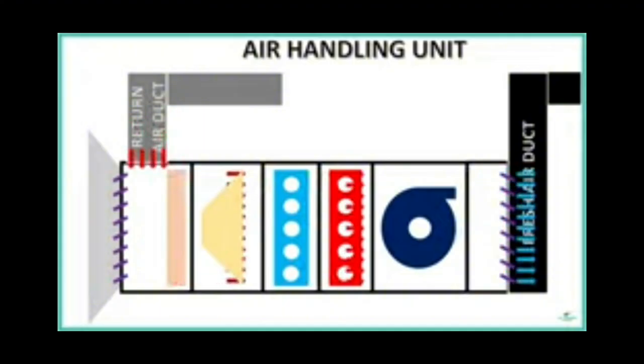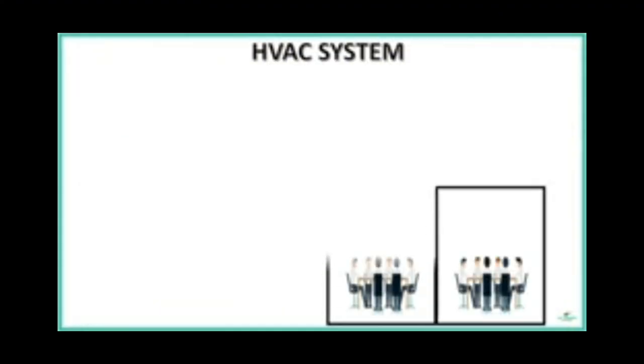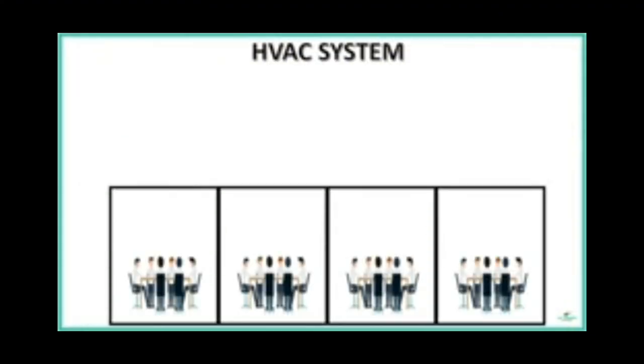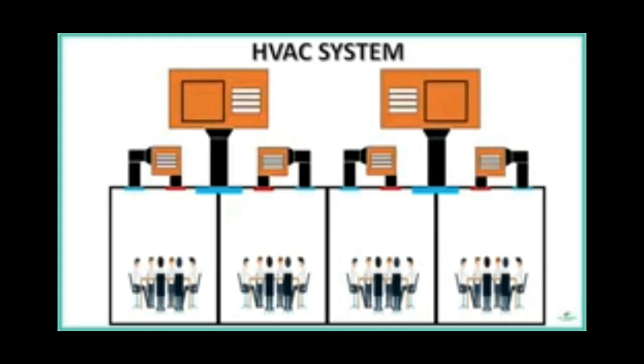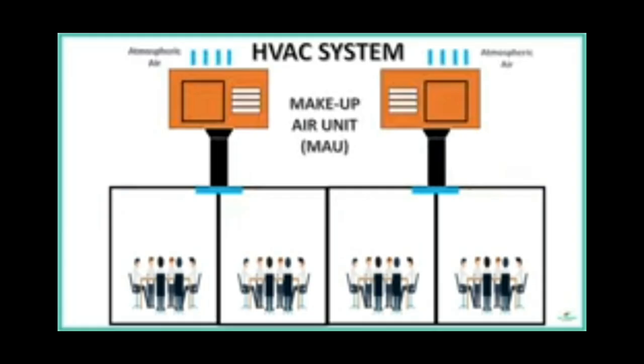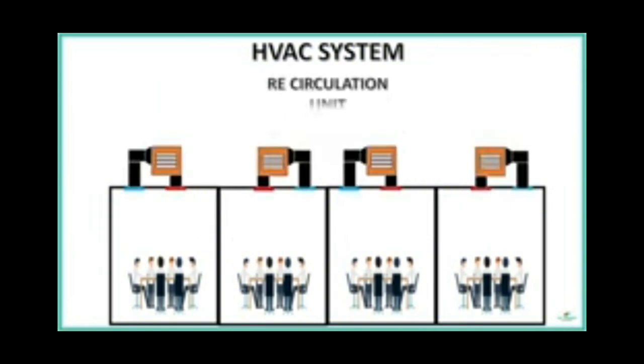But the main disadvantage of an AHU is that it can't provide good results in a large area of space. In these cases, the function of the AHU is split into 2 different units. An MAU, or makeup air unit, takes the fresh air from the atmosphere, filters it and delivers clean chilled air into the space. These systems ensure the availability of fresh air and eliminate the negative pressure build-up inside the space. An RCU, or recirculation unit, maintains the chillness inside the space by recirculating the available air inside the space.